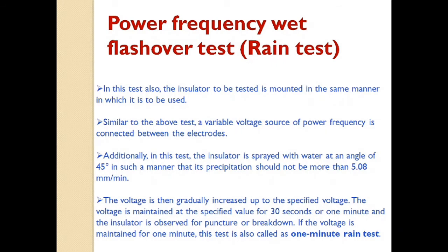Next one, power frequency withstand test or rain test. In this test also the insulator to be tested is mounted in the same manner in which it would be used practically. Then the terminals of the variable power frequency voltage source are connected to both the electrodes of the insulator.